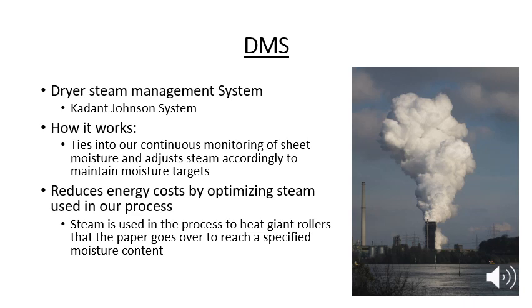Additional systems are tied into our DCS. One is provided by a third party, called Dryer Steam Management, or DMS. This system is tied into continuous monitoring of sheet moisture and adjusts the steam we use to dry the paper in order to maintain the moisture target customers request. This allows us to optimize steam use. Steam production consumes most of the energy in the mill, so we get a good rate of return on anything that helps continuously minimize and optimize our steam usage.